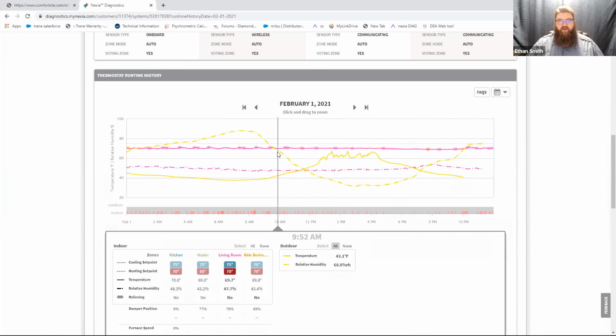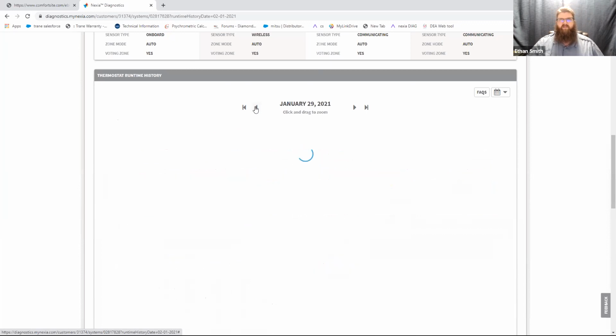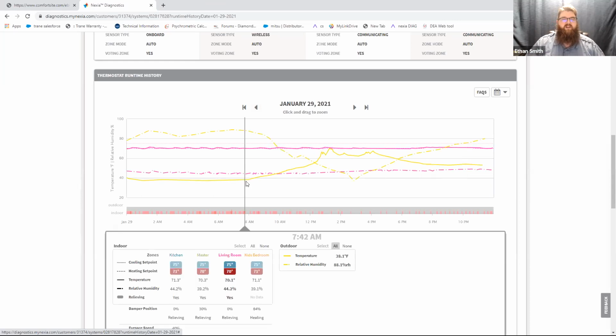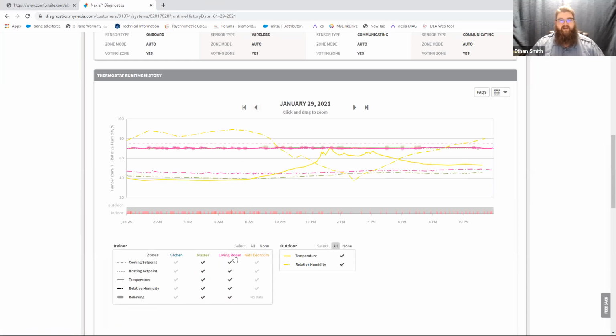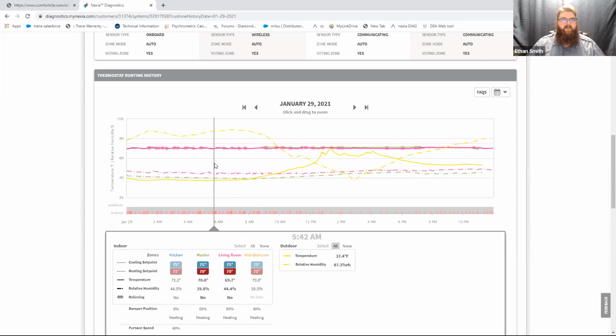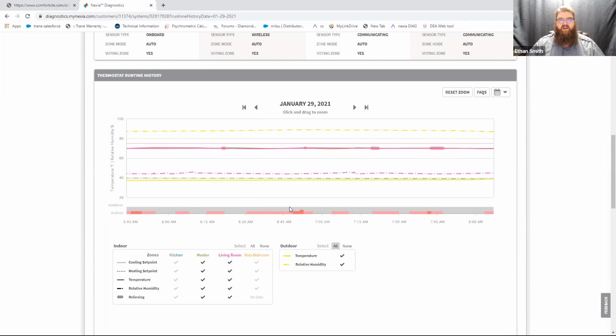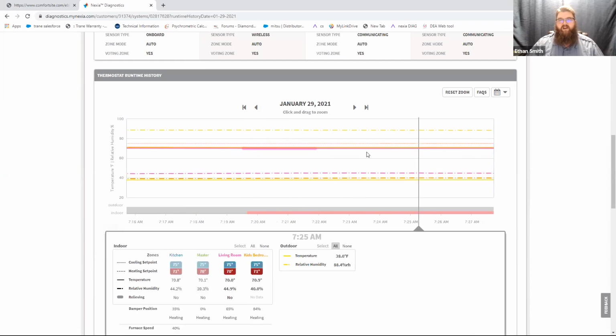But you know, we can get whatever data we want out of this thing, guys. You can go to anywhere you want, and it will help you with your diagnoses to have that background context. Because invariably, when we get complaints about zoning, it always goes with this big set of caveats or set of circumstances that we're hardly ever able to replicate in the field. They'll say when the master bedroom and the living room are calling at the same time, it has a problem. Well, this allows me to select that master bedroom and that living room and see what they're talking about. In this case, it's most likely we're going to get that call that anytime the kid's bedroom's running, we get air out of all the other vents. Well, yeah, it's because the kid's bedroom's a little small, and so it relieves into all the other zones. We can see that fatter line right there where we're getting relief air into my living room zone from the kid's bedroom.